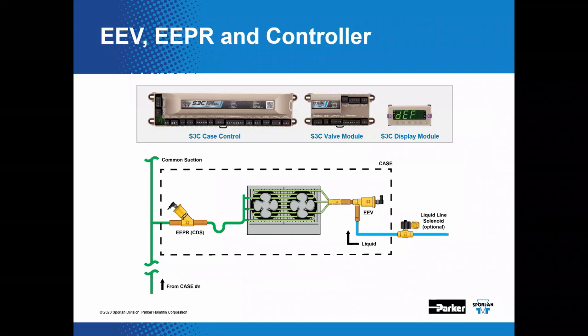Correct. Now, even though the EEV can influence both discharge air temperature and evaporator superheat, multiple evaporators running at temperatures above common suction just might show enhanced performance if we included an electric EPR. The case shown in the diagram below could be the lead case in a lineup.